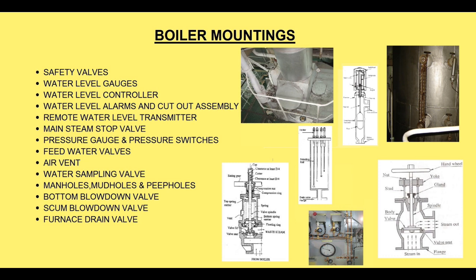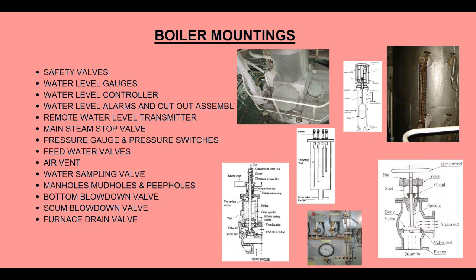Normally two water level indicators are fitted to each boiler, with a remote level indicator at a convenient control position. Blow down valves are fitted in pairs to the water drum to enable water to be blown from the boiler. This is to reduce the boiler water density.